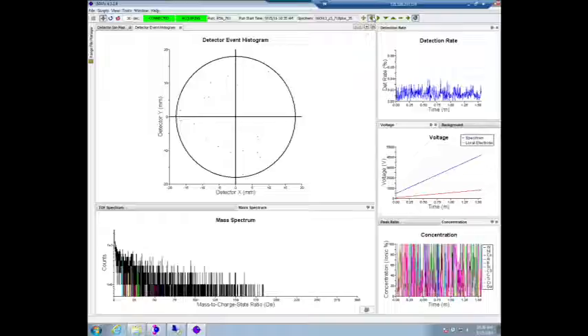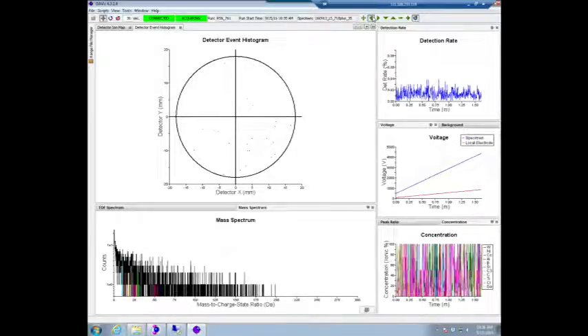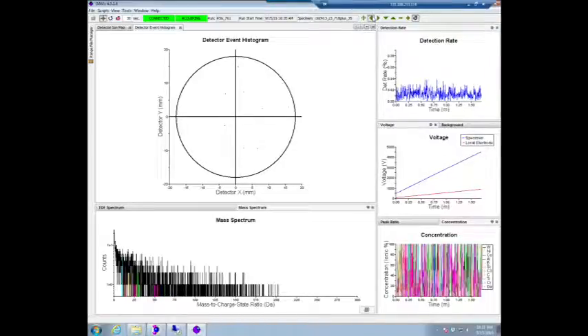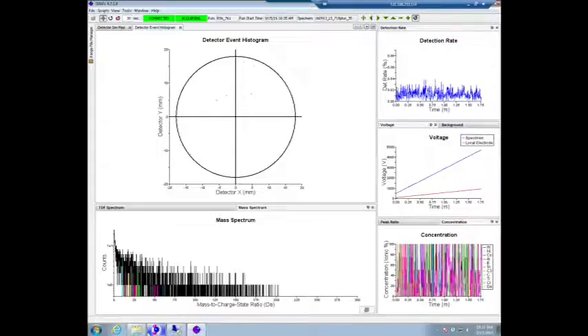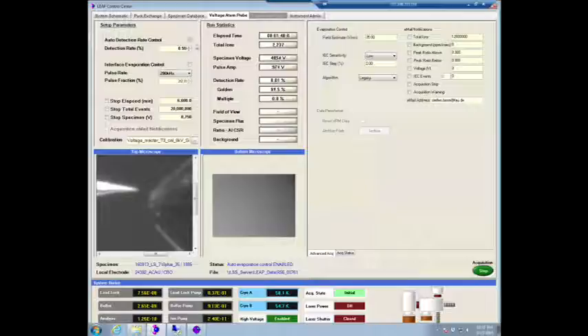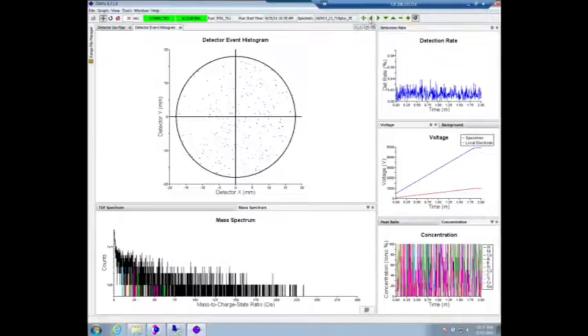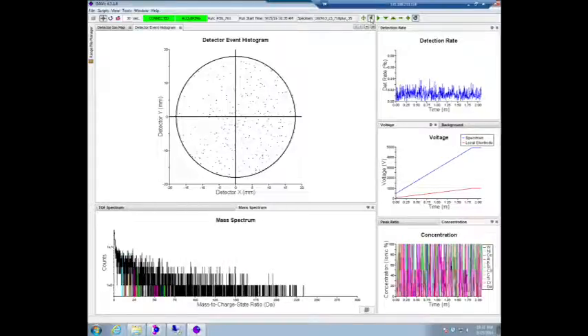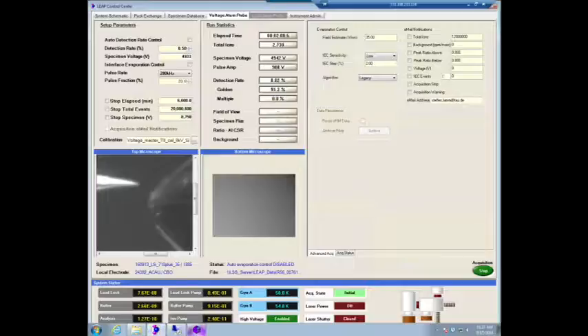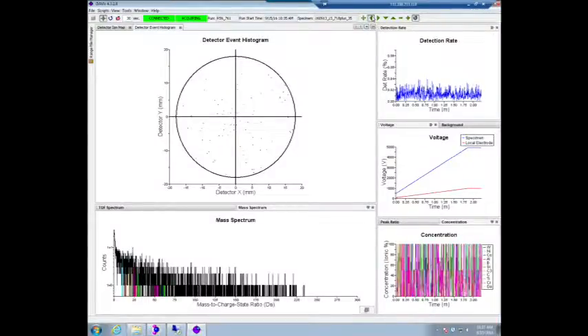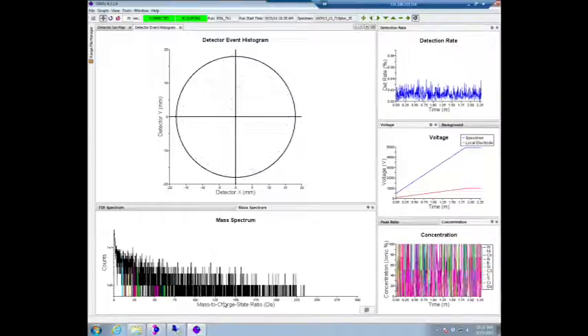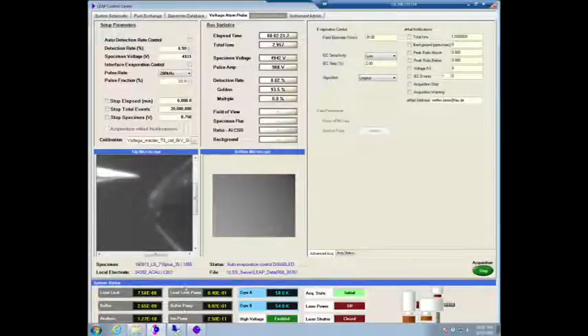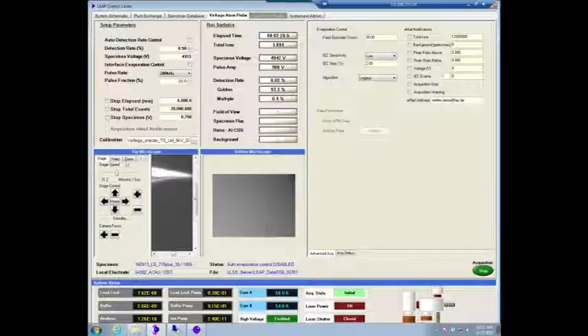Okay, so we're going to try the brute force variant of just moving the sample left and right, and see if we can get any signal. But for that purpose, I should probably switch off the auto evaporation control, the detection rate control. So now it just runs at 5 kV no matter what happens. The other problem that we're dealing with is, of course, that we can only see one program at a time. I think that's not the right axis. Yeah, well, now it's obviously the wrong axis, so I need to go to the other one. But I guessed wrong which one's which. You can shift this in the right click. Right click here. Oh yeah. Right.